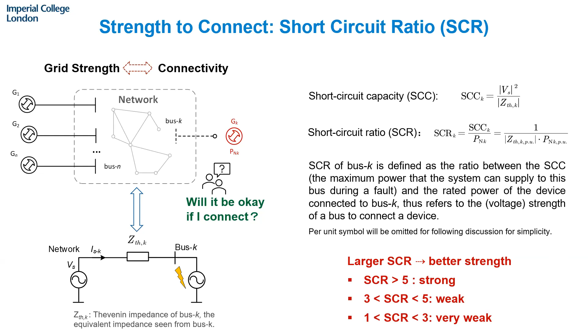There are other understandings of short circuit ratio from different perspectives. If you think of connecting a voltage source to the system trying to deliver its nominal power, then we know that when the power angle reaches minus 90 degrees, the system reaches its maximum absorbable power. So the short circuit ratio is actually the ratio of the maximum absorbable power of the grid to the nominal power of the device.